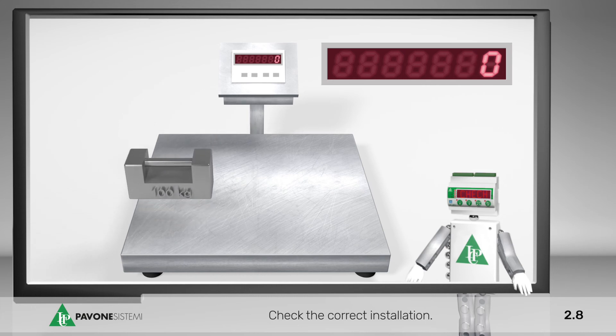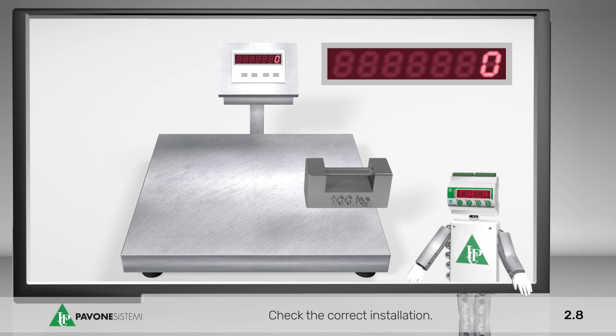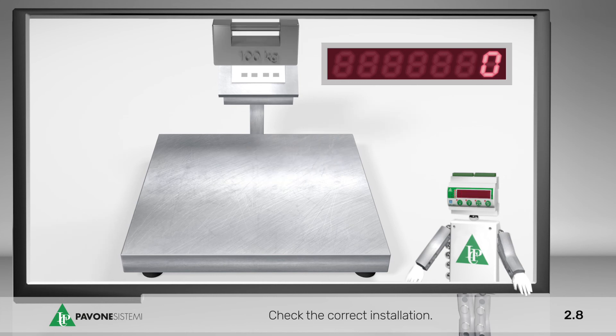The indicated weight should be repetitive and the weighing system should return perfectly to zero before the performance of each load test. This simple test assures that the weighing system is reliable.